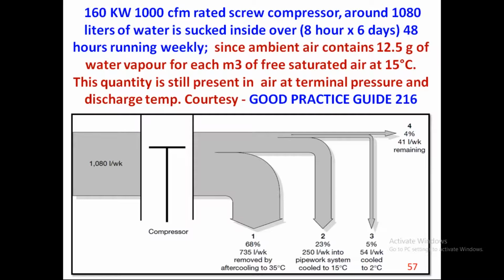But you will find from this diagram, thanks to the good practice guide, it's an excellent guide, where we can understand the post air cooler delivers the maximum water that is to be removed from the compressed air. So your post air cooler has to work effectively in the compressor, and that is kept inside the compressor hood and is not accessible to the operator. That is the irony, or the satire, of it. If the post air cooler is made to work effectively, then the compressor will perform excellently.